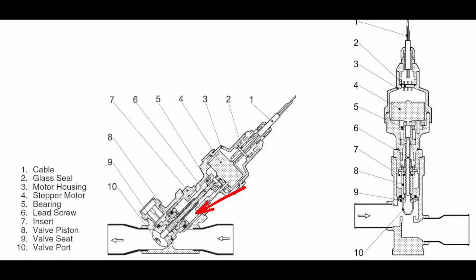And then you apply refrigerant flow and refrigerant force through there, which most of the time is going to be coming against the valve piston, pushing down on it, making it want to open less, right? Most of these valves, that's how the cycle goes through them. You can see that here in this process. The valve is trying to open up, but our refrigerant force is pushing down on it. So if we're at a standing state, not even running or flowing refrigerant, but we can't even open the valve, how much worse is that condition going to be when we start flowing refrigerant? You can also see that here. We're closing in a downward position, flowing out to the right side here, but we're coming in and flowing down.